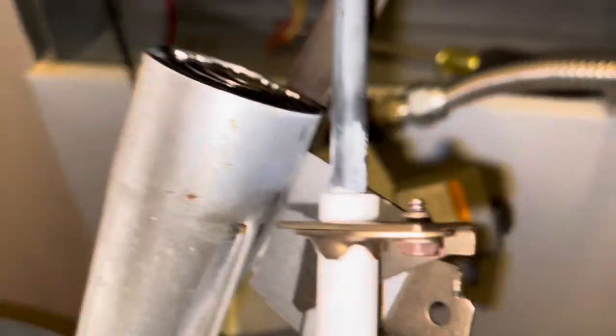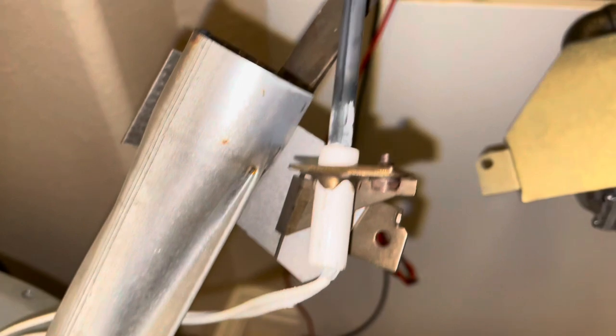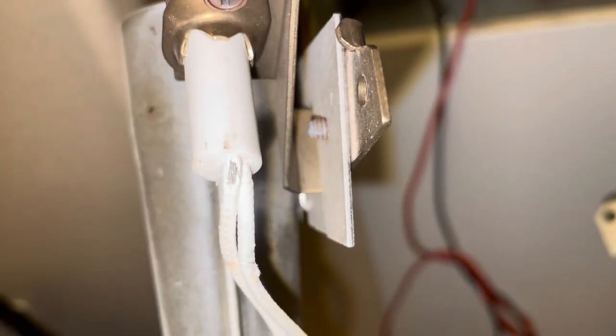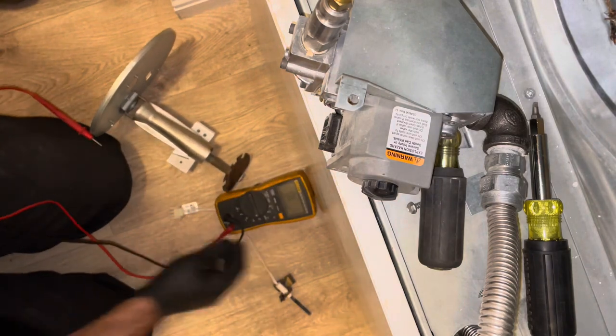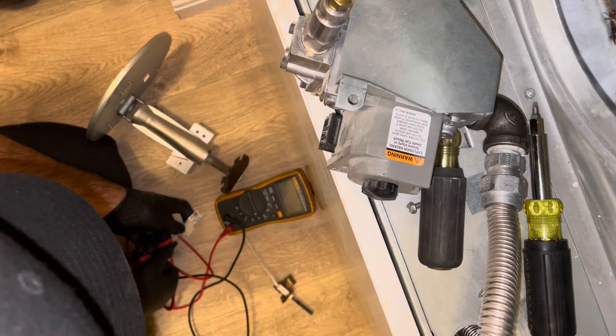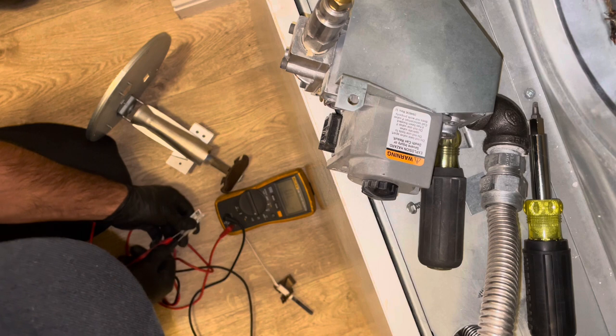It looks a little cooked. We're definitely getting power, but this igniter does not want to ignite. Burner is clear. Some chewed up wiring. Let's ohm this thing out. Yeah, this igniter is no good.